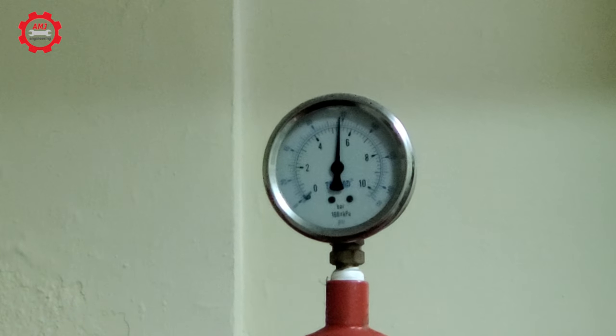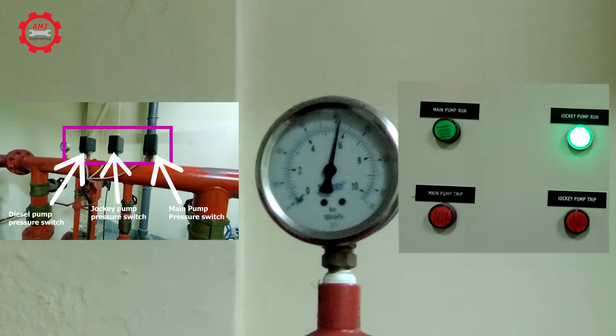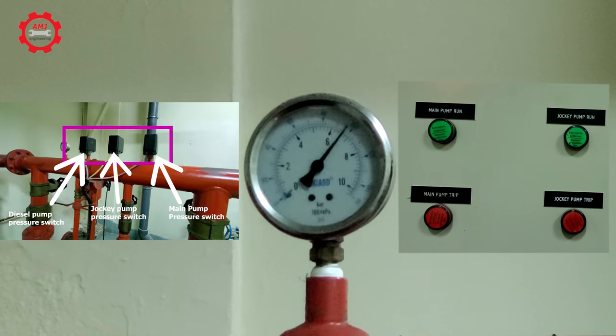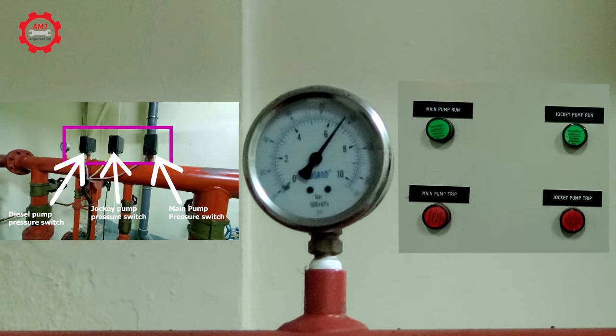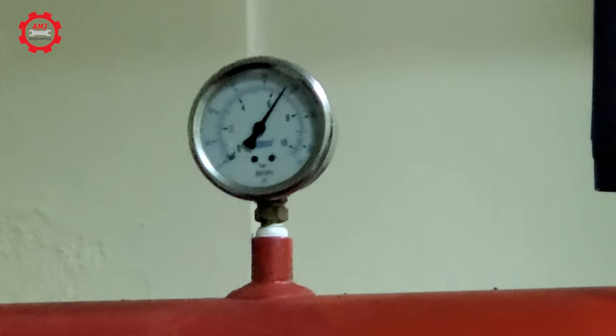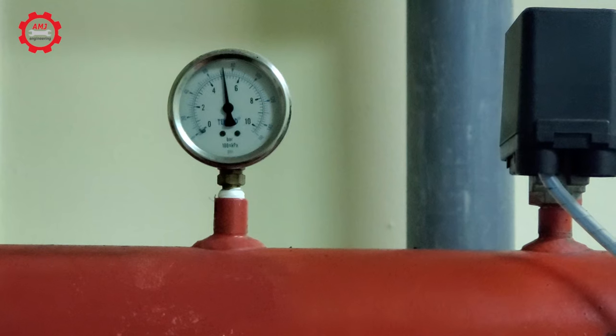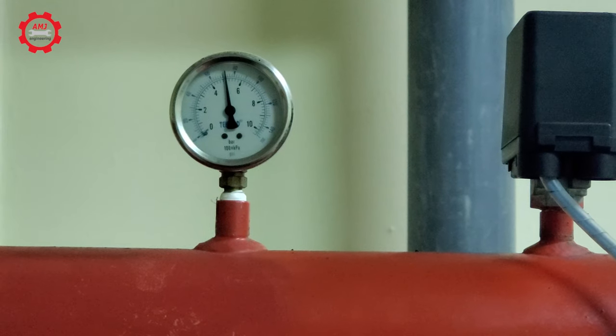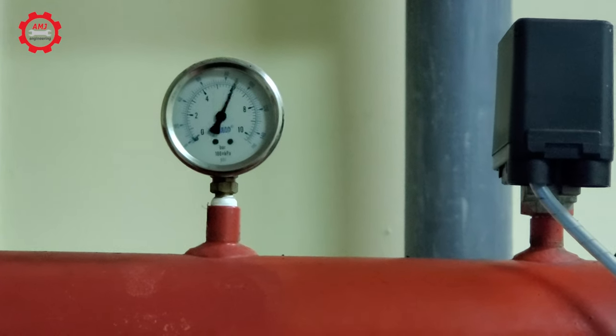When the water pressure drops below the preset level, the pressure switch energizes a starter which activates the jockey pump. Correct water pressure is therefore maintained at all times. If a fire should start, the pressure will continue to drop and the main fire pump will start.